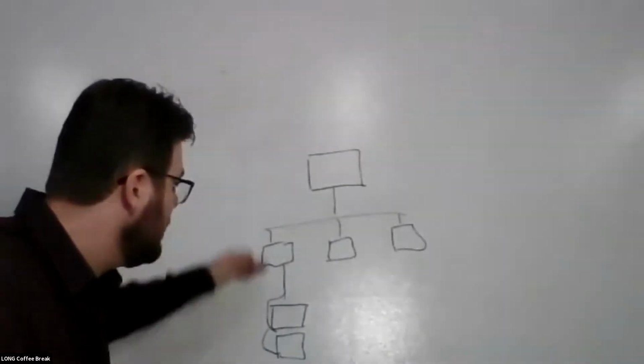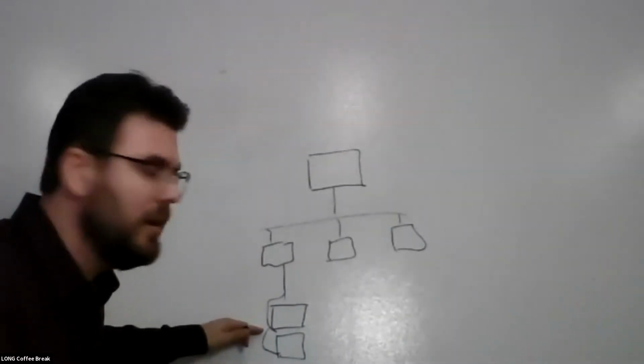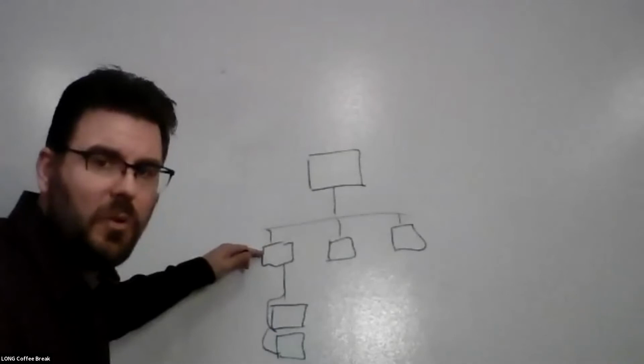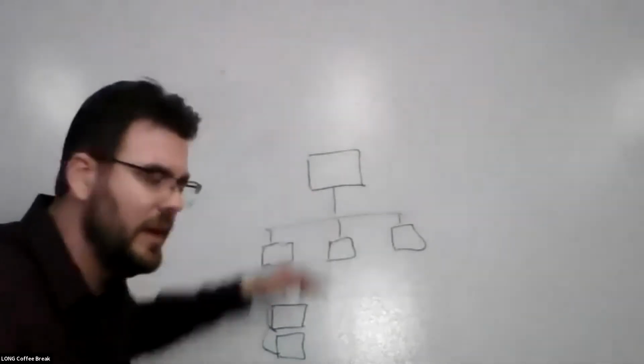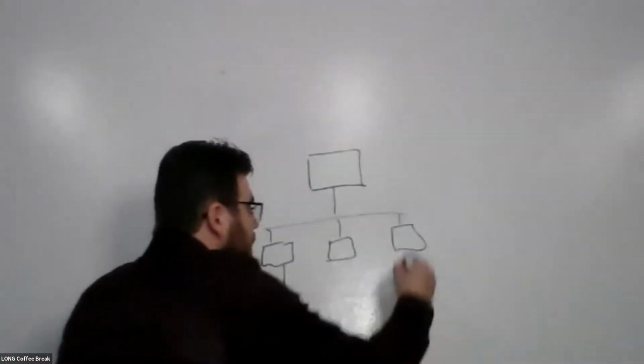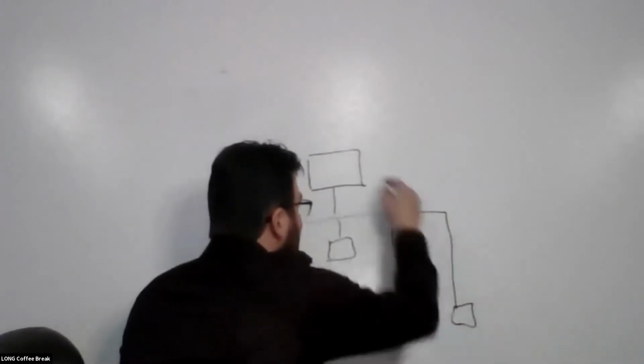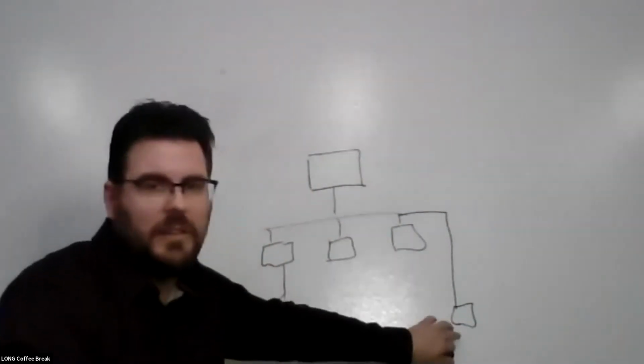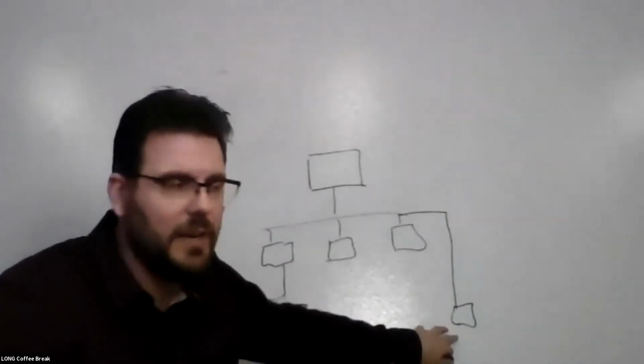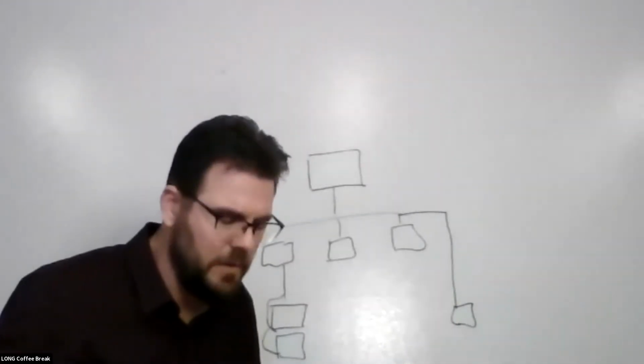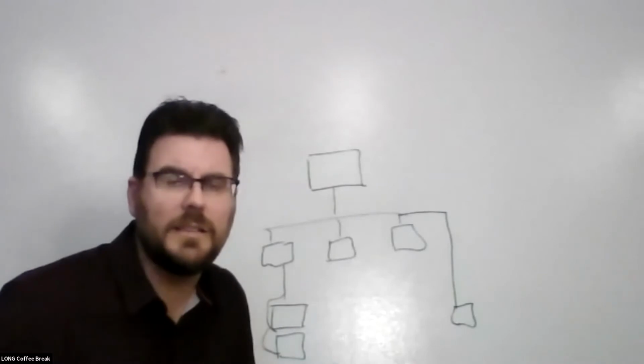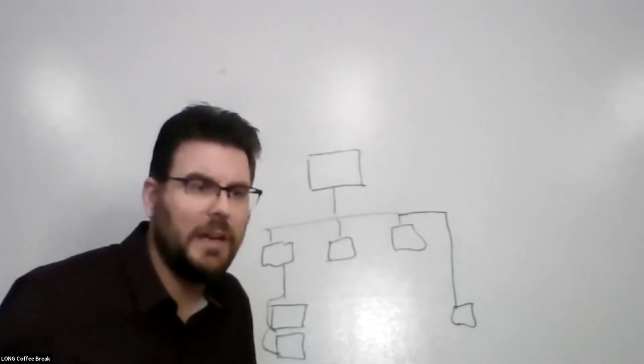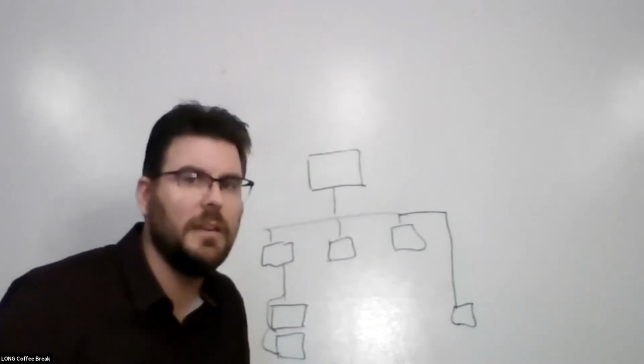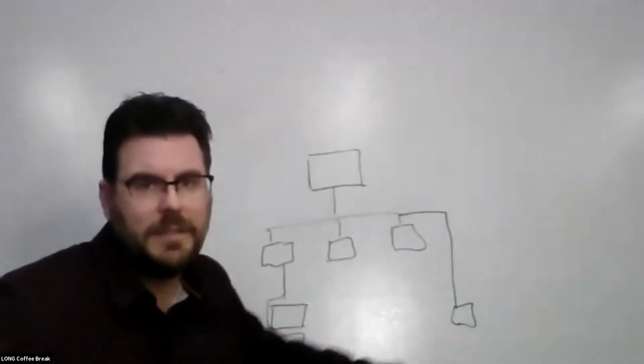Typically the older hierarchy is this goes through the equipment controller and then up to the head-end server. Now we also have the ability to go BACnet all the way down from the server to an individual VAV box controller. So that opens things up, whether it's talking BACnet, BACnet MSTP, or BACnet IP, you can get down to lower level devices.